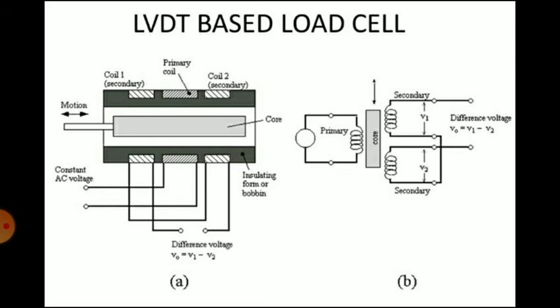Then the LVDT type load cell. You can see the LVDT has a primary coil and two secondary coils, and in between there is an iron core. The pressure to be measured is applied to the iron core or the iron rod. So bellows can be combined with an LVDT to give a pressure sensor with an electrical output.